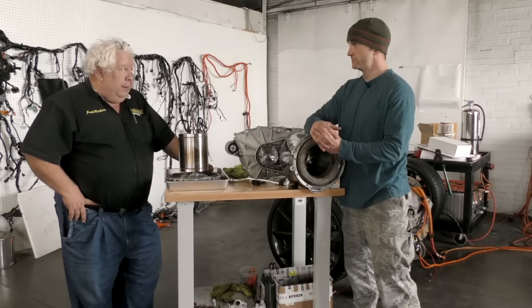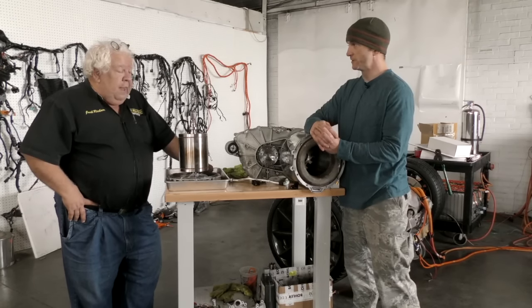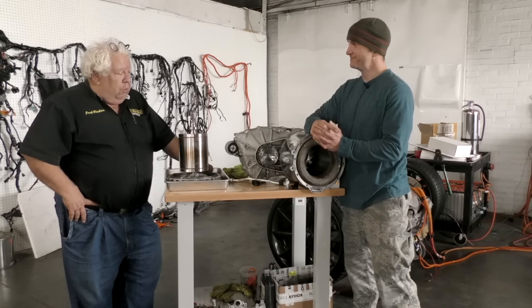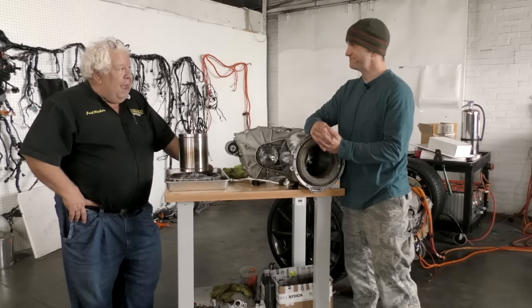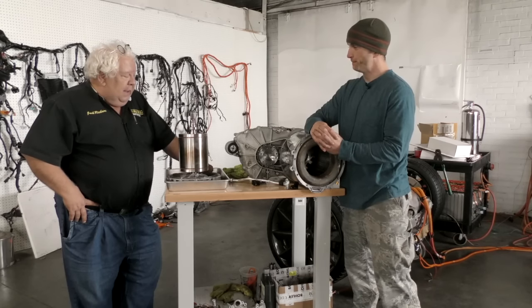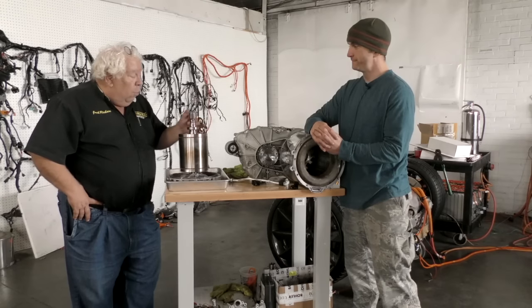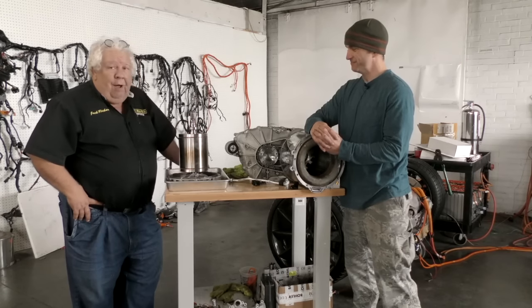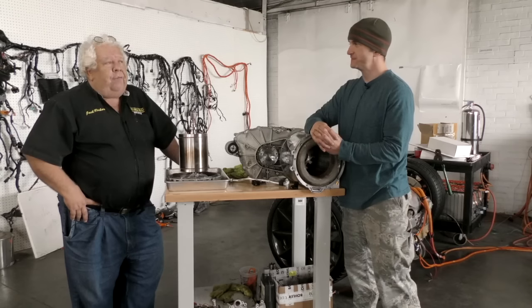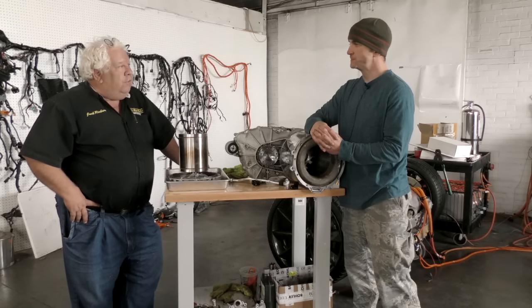There's some lubricant in there, but that's where I'd go if I was an electron. If I was on a rotor and wanted a path to ground, I have two bearings to pick from. And so apparently this one wasn't the one picked, but the other one may have, and those currents could cause erosion of the bearings and premature failure.